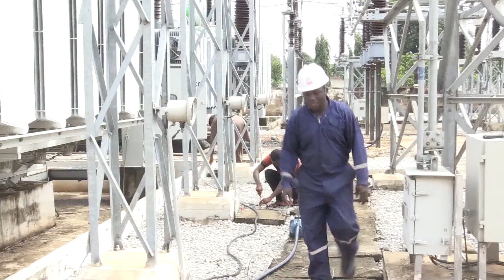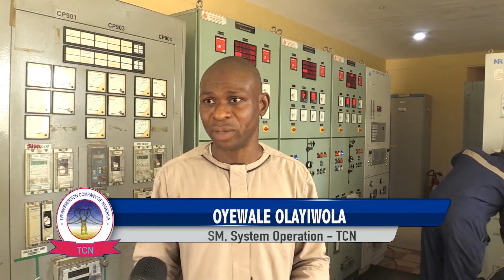So when they come, they have already applied to us, and the application has been sent to our area control. The area control, having made a plan on that application, sends it to them. We now have to call them back to seek approvals based on their planning. If they are okay with it, they now apply for us, and we go ahead and take out the transformer. As an operator, immediately I get approval from them, I now take out my transformer.